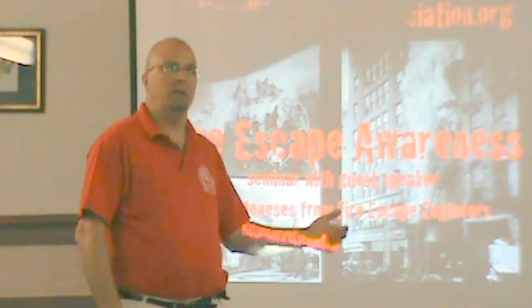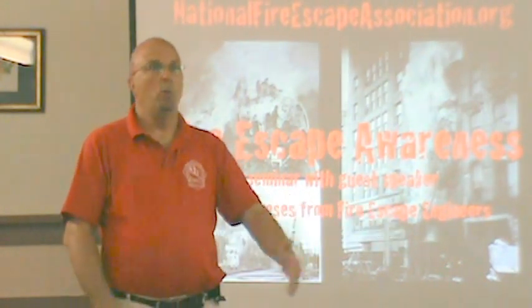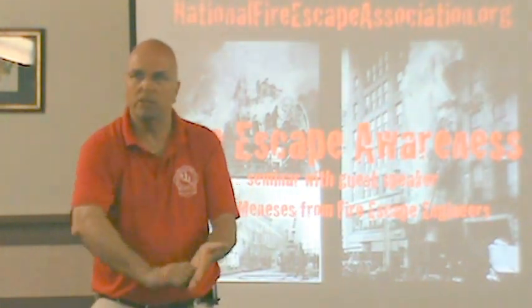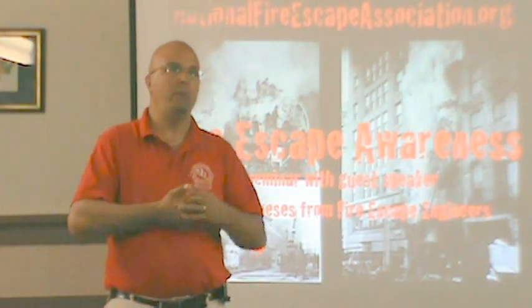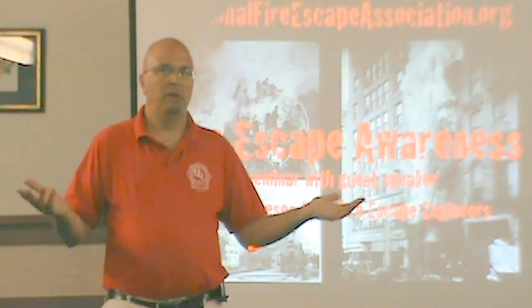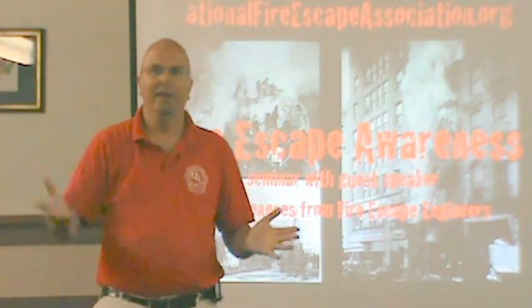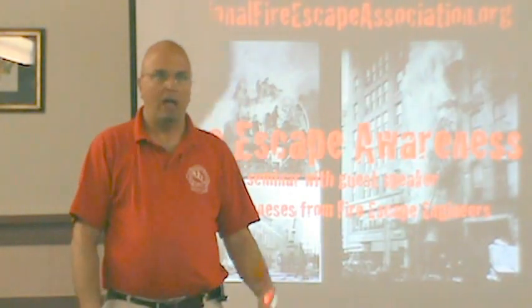The law is very clear. The authority having jurisdiction shall accept by law test or other evidence of strength. We've never given them any other evidence of strength or a load test, and yet our signature kept going on the bottom of these documents, and the only thing that saved us is the fact that we don't have fires every day. But if you put every building in LA through at least one fire every year, mandatory, like they set your building ablaze, you'd have a lot of dead people or a lot of dead firemen on the ground, because a lot of these would fail.